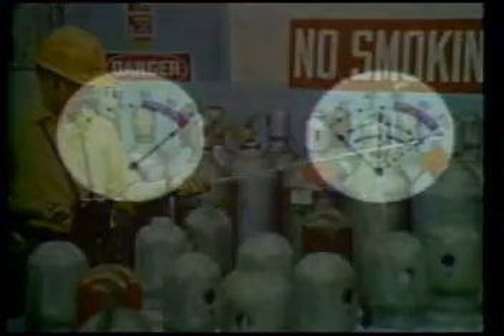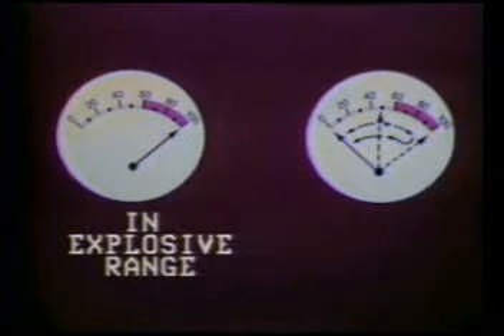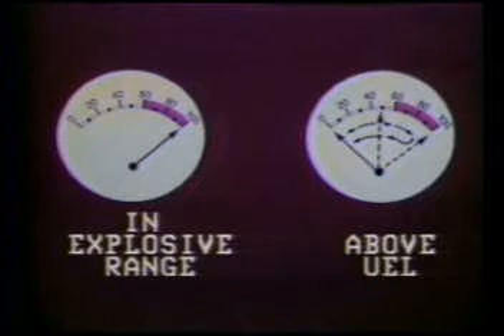To recap, if the meter needle goes upscale above 100% and stays there, the sample is probably in the flammable or explosive range. If the needle moves rapidly across the scale and returns to 0 or below, the concentration is above the UEL.